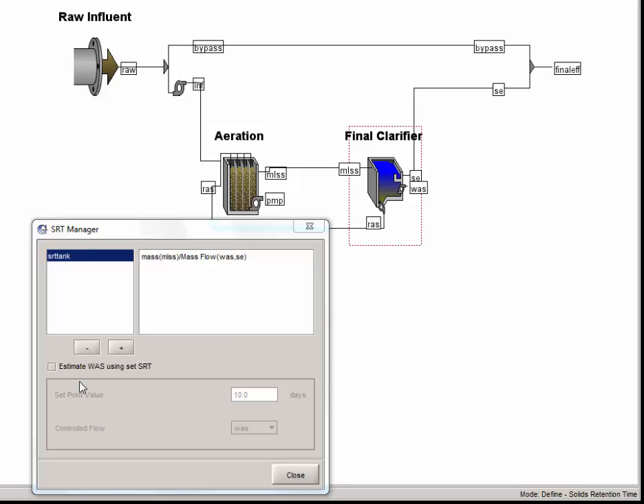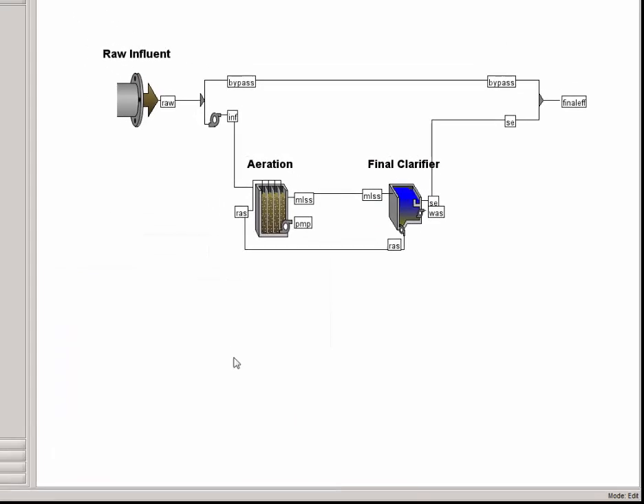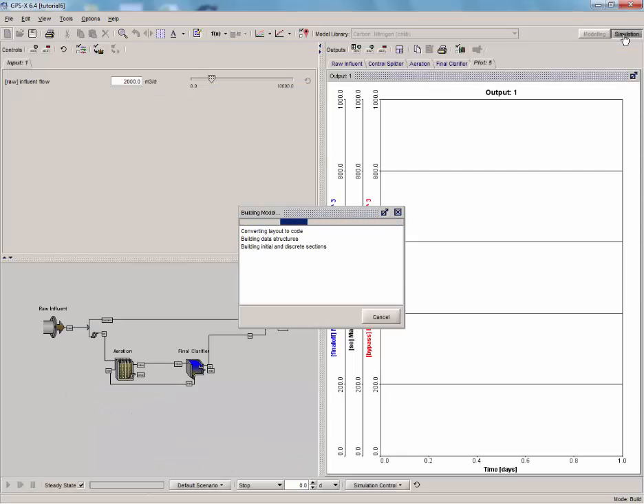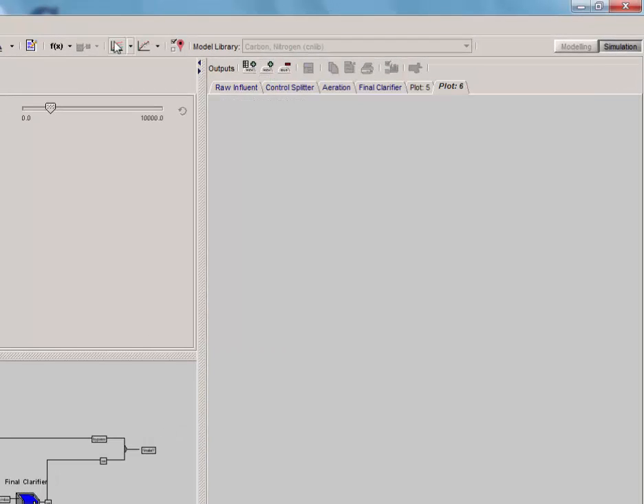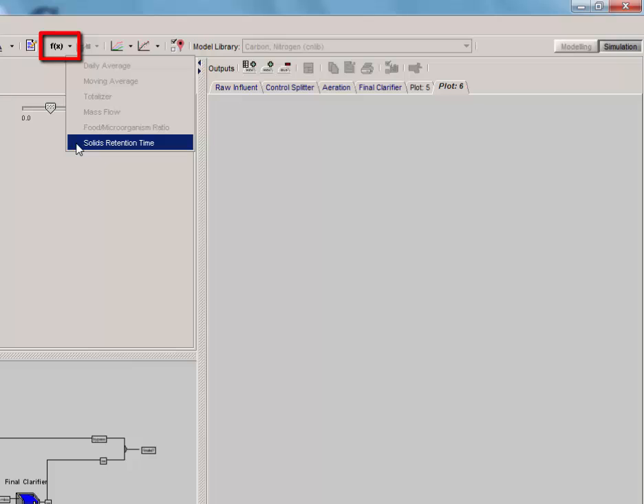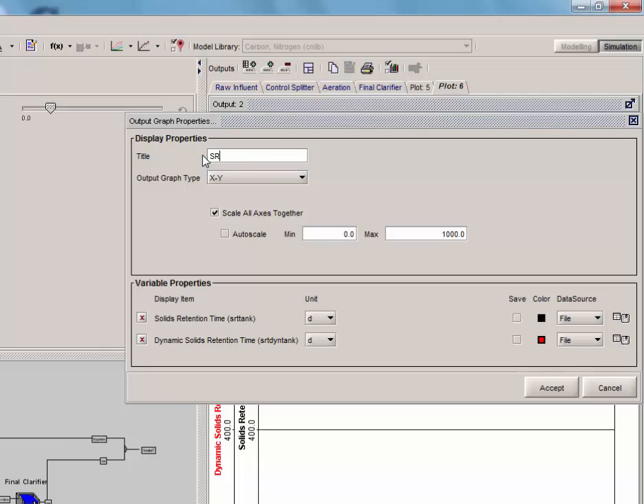The SRT manager also provides an option to create a process controller for SRT. This option can be accessed by clicking on the estimate WAS using set SRT checkbox. A desired SRT and the desired controlled flow can be selected. Make sure that this option is unchecked and close the SRT manager window to accept the equation. Now that we have defined the SRT equation, save the model and click the simulation button and rebuild the simulation code. Once the model code is generated, we need to set up SRT as an output parameter. To do this, click on the Define button and select solids retention time to bring up the SRT manager window. Drag the SRT variable from the window to a new output graph. Resize the graph. Go to the output graph properties menu to set an appropriate title and a reasonable scale, say around 30 days retention time.